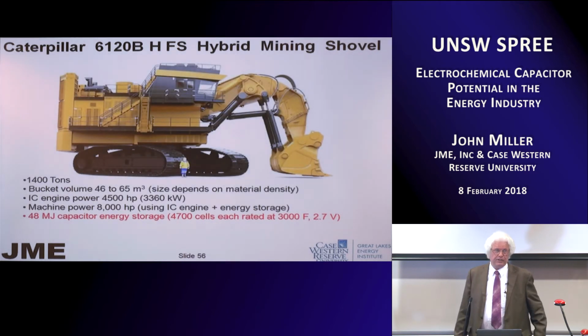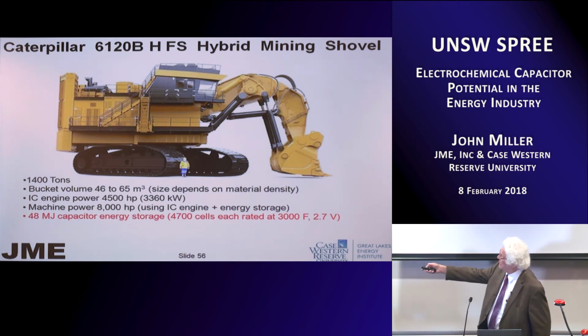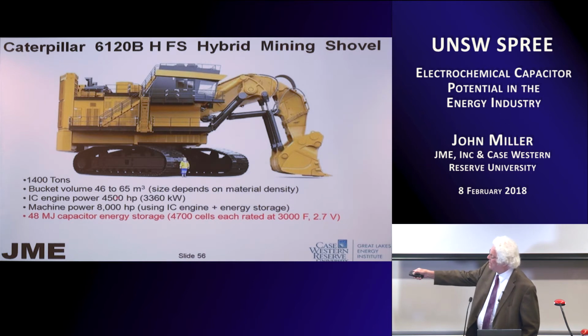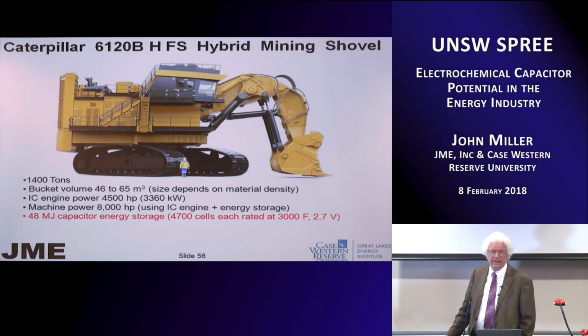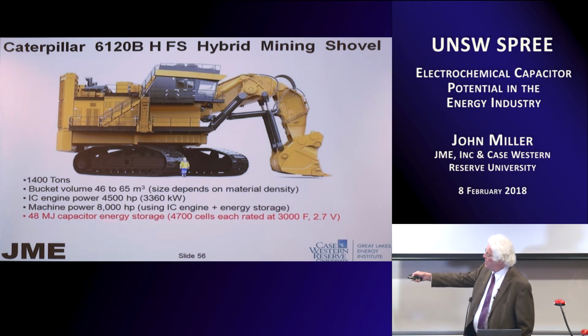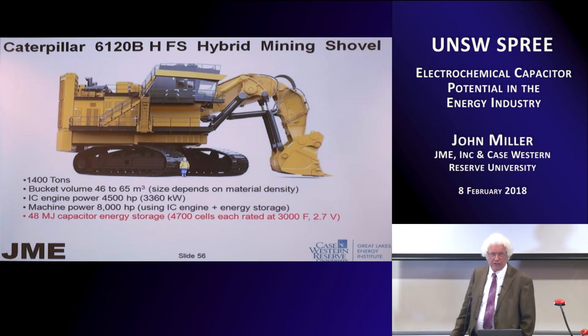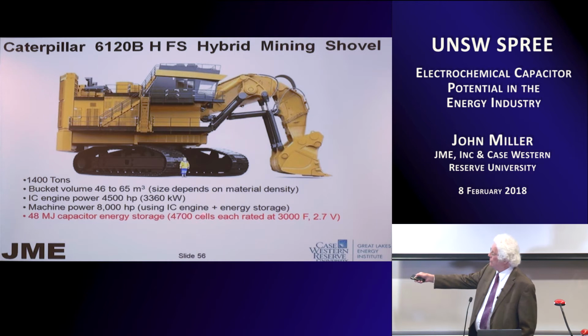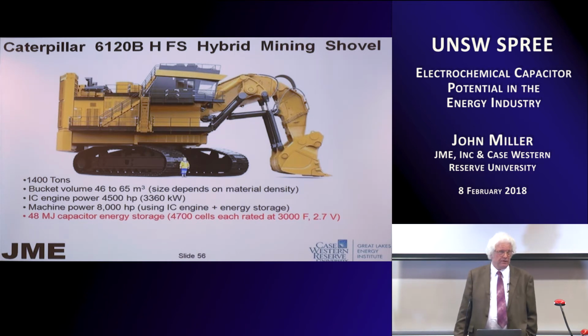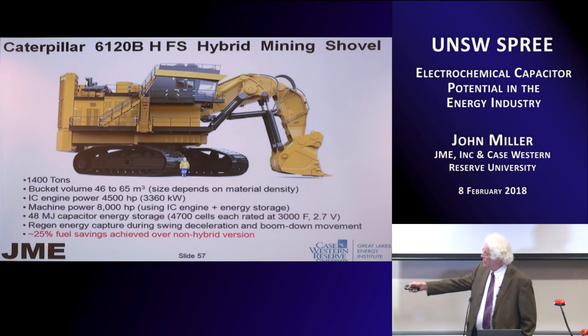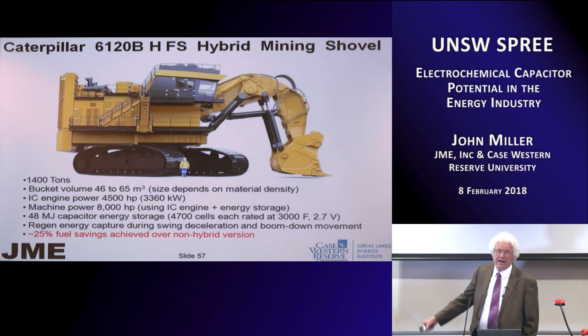This is the largest example of hybridization I've seen - a Caterpillar mining equipment, and you can see the people for scale of how large this device is. It has a 4,500 horsepower engine, but the machine power is over 8,000 horsepower, so it's taking 3,500 horsepower from stored energy. That's done by 48 megajoules of capacitors - 4,700 cells of the type I showed you, 3,000 farad size.